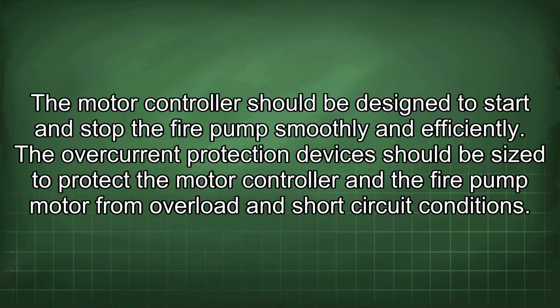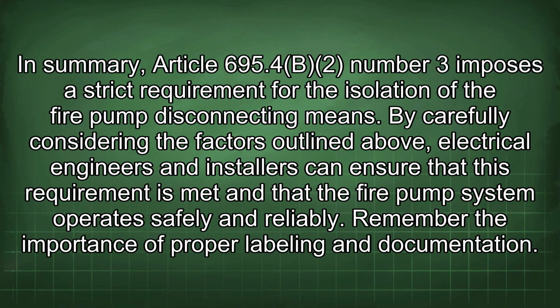The motor controller should be designed to start and stop the fire pump smoothly and efficiently. The overcurrent protection devices should be sized to protect the motor controller and the fire pump motor from overload and short-circuit conditions. In summary, Article 695.4 B2 number 3 imposes a strict requirement for the isolation of the fire pump disconnecting means. By carefully considering the factors outlined above, electrical engineers and installers can ensure that this requirement is met and that the fire pump system operates safely and reliably. Remember the importance of proper labeling and documentation.